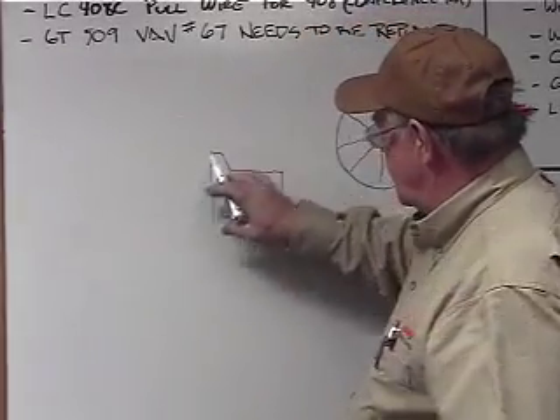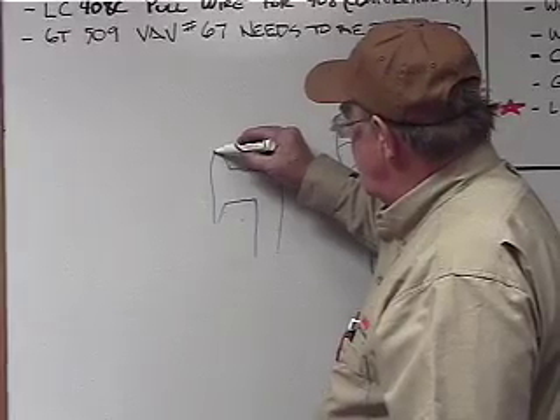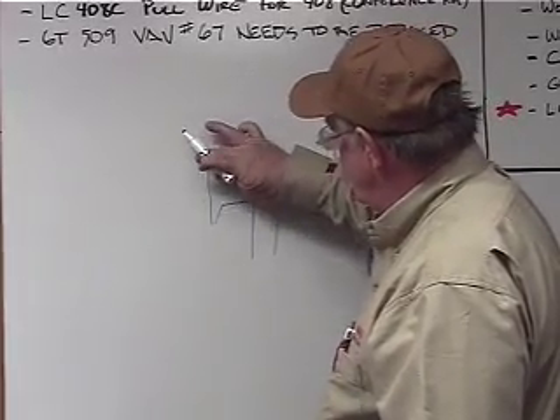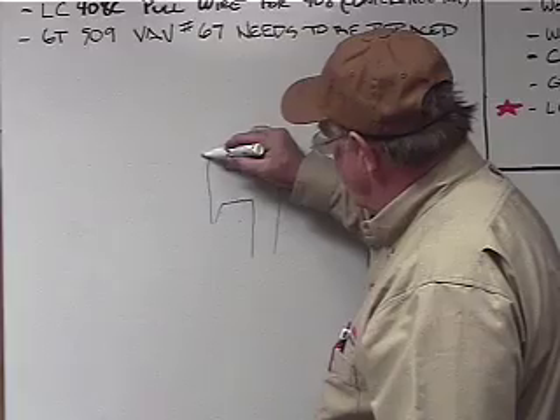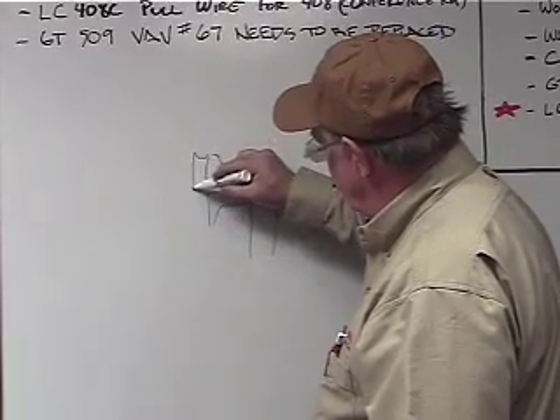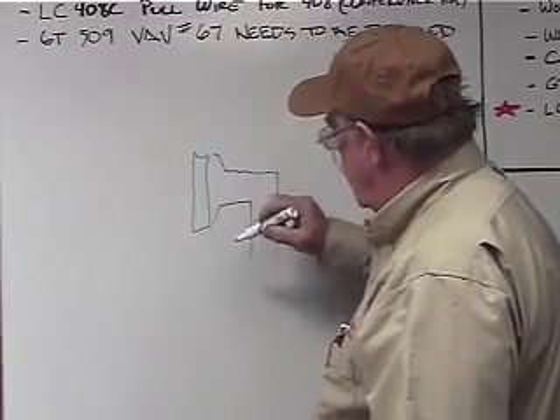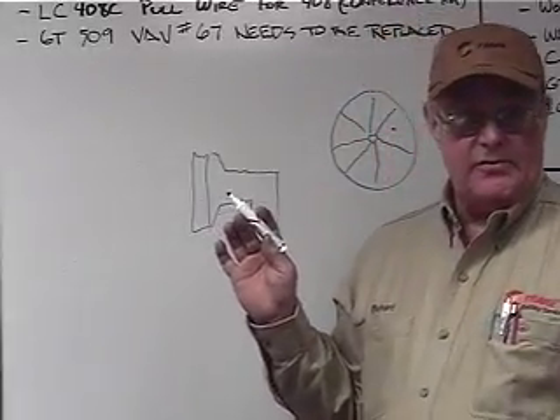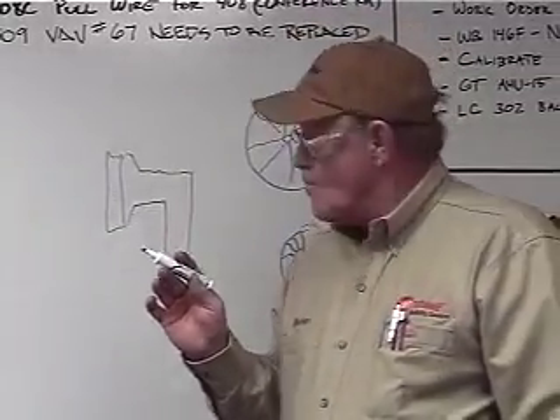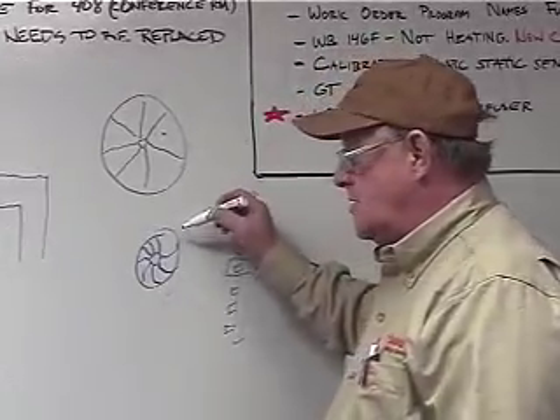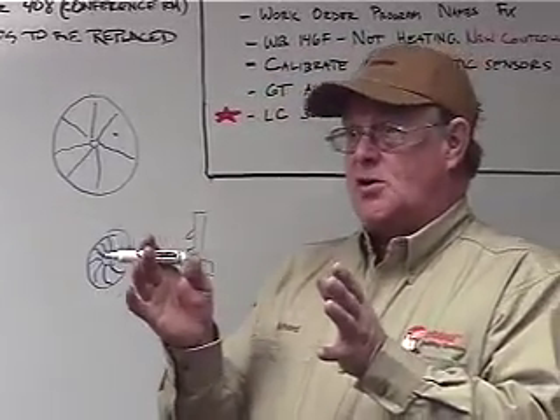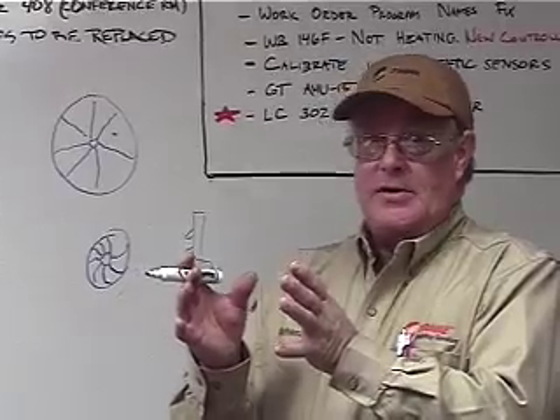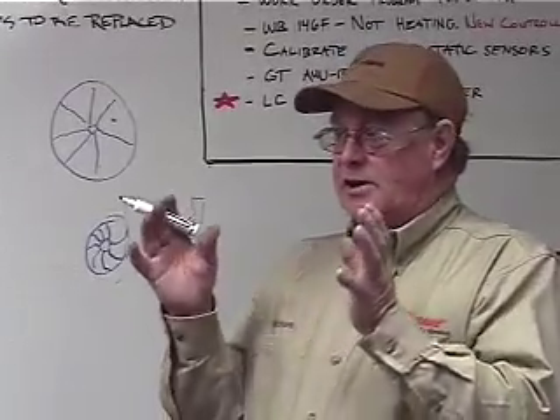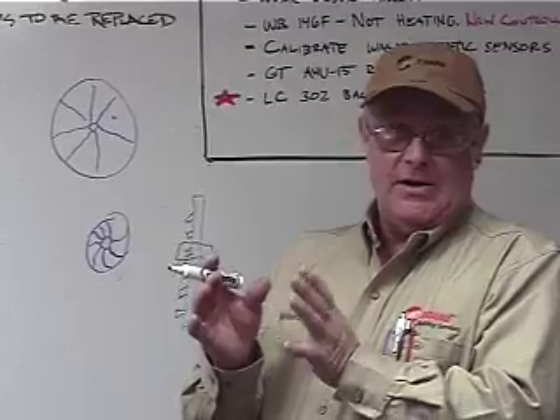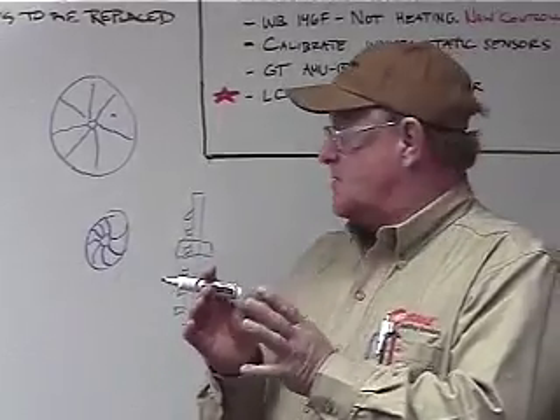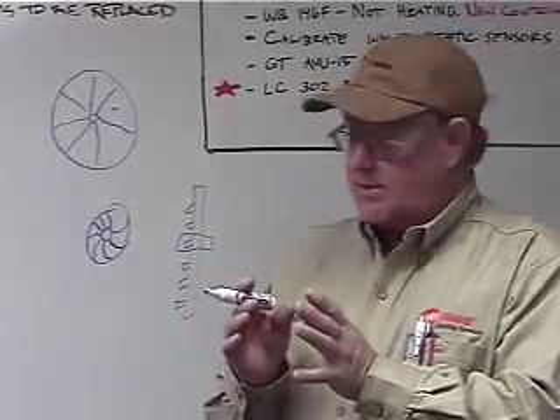That's where all this stuff is. You're going to see an indentation where it kind of comes down and goes into another volute. There's another impeller in there, which looks just like this. The only thing is, the openings start getting tighter. So what we're doing is we're actually compressing the gas. It's a low pressure gas, and this is what creates your higher pressure gas.